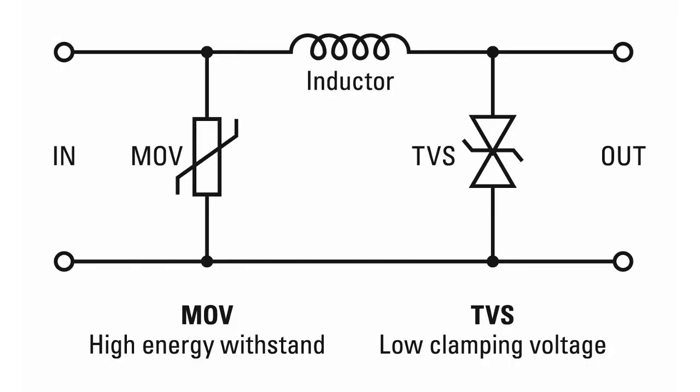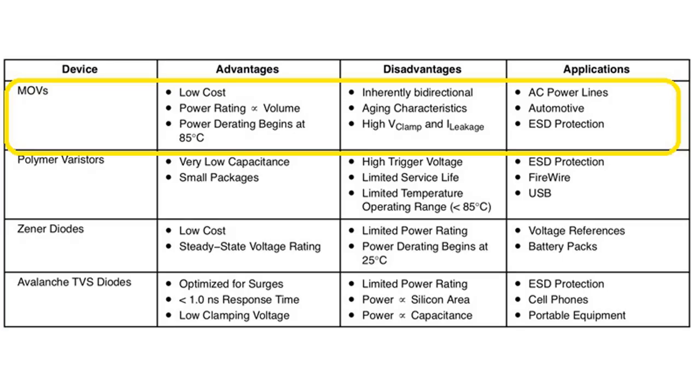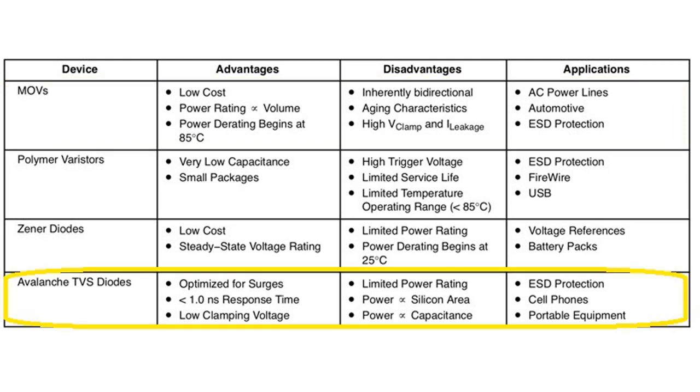Let's see the difference between MOV and TVS diode. MOVs are most often used on the power mains to protect downstream electronics and electrical equipment from direct and nearby lightning hits. Silicon TVS diodes are used extensively for protection across more sensitive data lines on telecommunication and microprocessor-based monitoring systems.